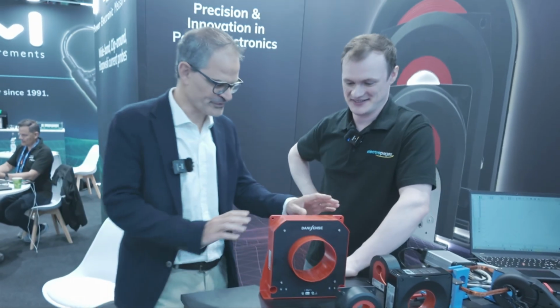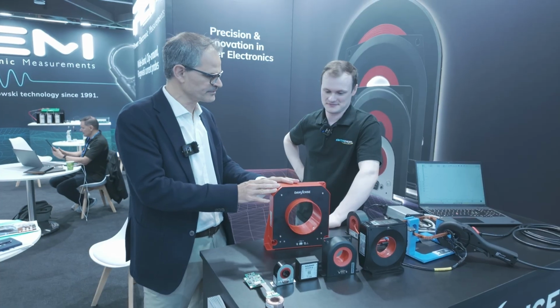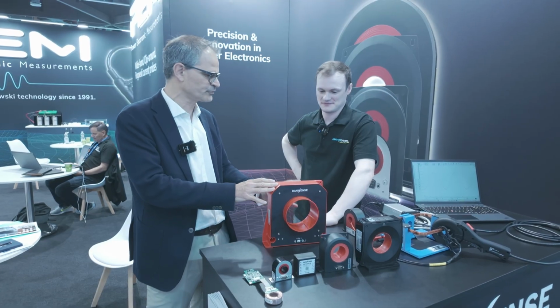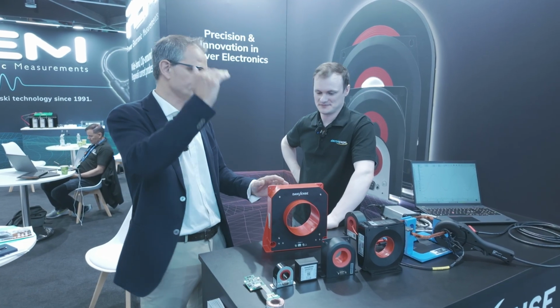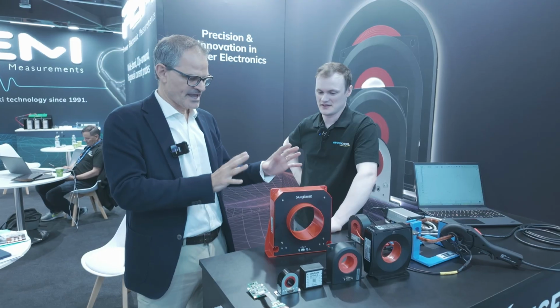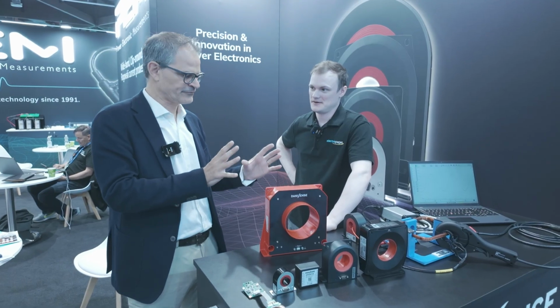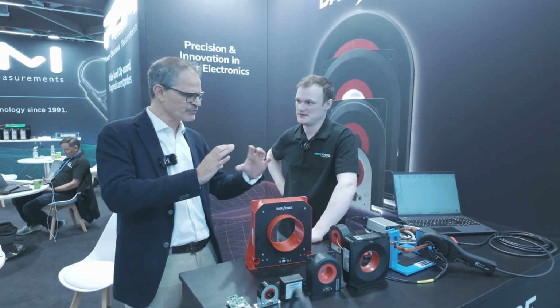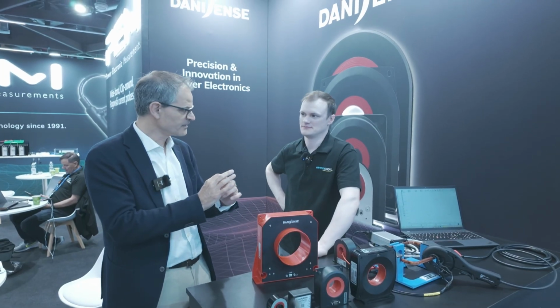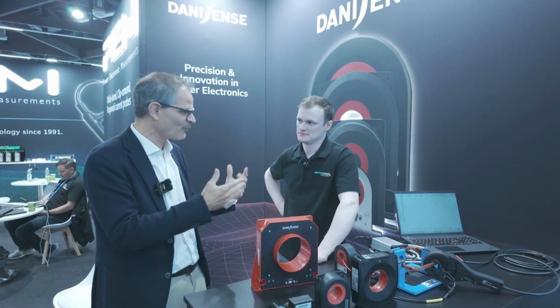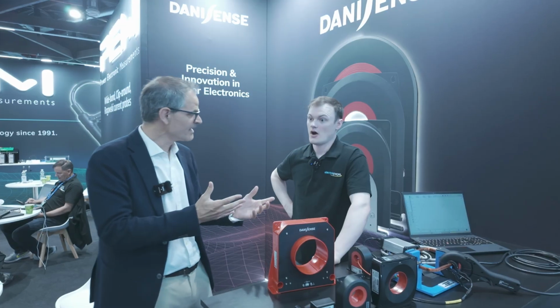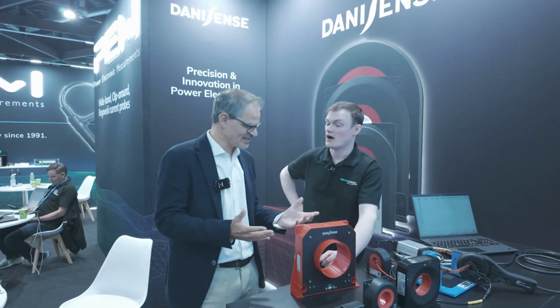Excellent point. So this product has been specifically designed for high power applications because we can measure up to 4,000 amp, 7,000 amp peak, and there is more and more request for large aperture measuring small current. So typically state of health for battery, supercap, and charging systems.